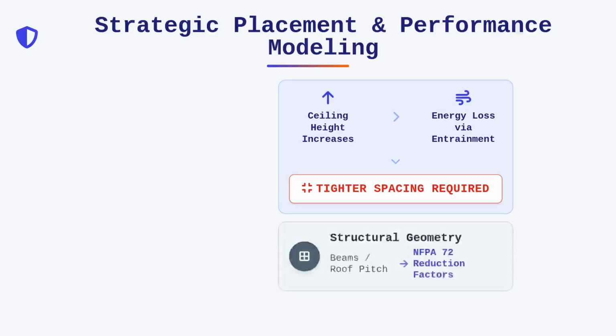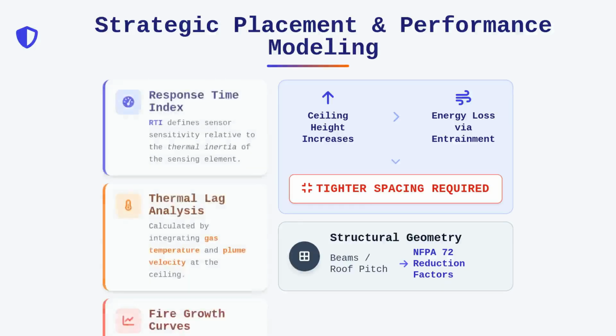Structural geometry, such as beams or varying roof pitches, forces us to apply specific reduction factors to the standard spacing guidelines found in NFPA 72. You should always look at the fire growth curve, often modeled as t-squared, to estimate how quickly the heat will breach the activation threshold of the selected device.